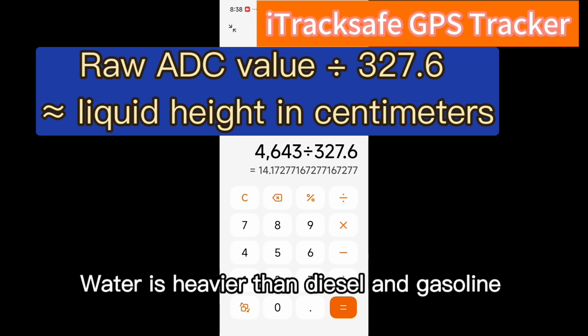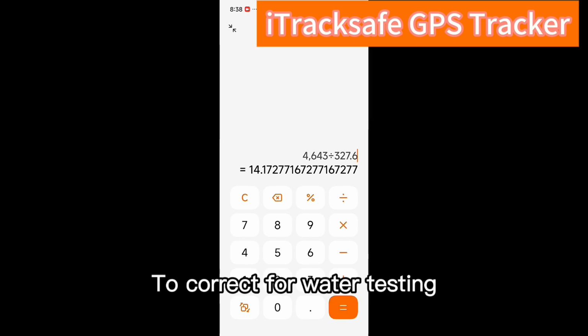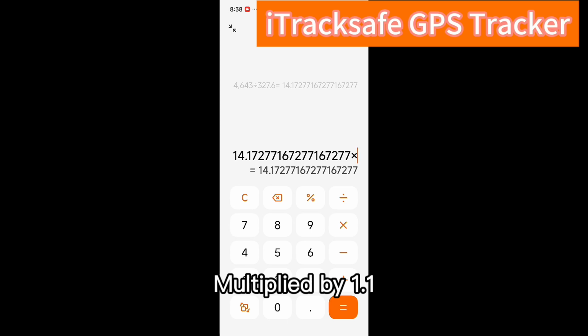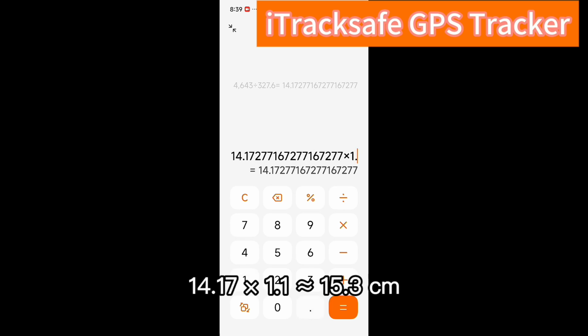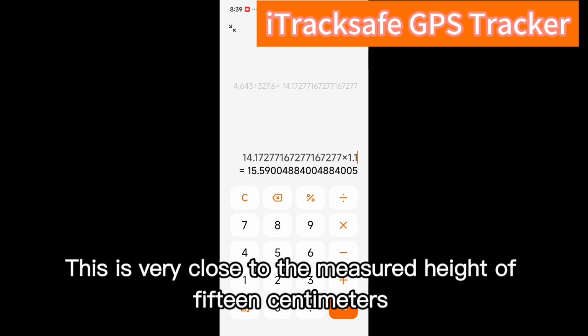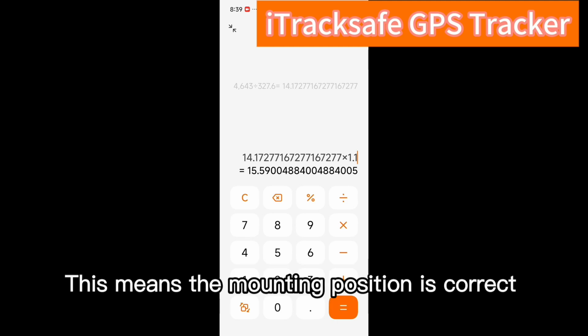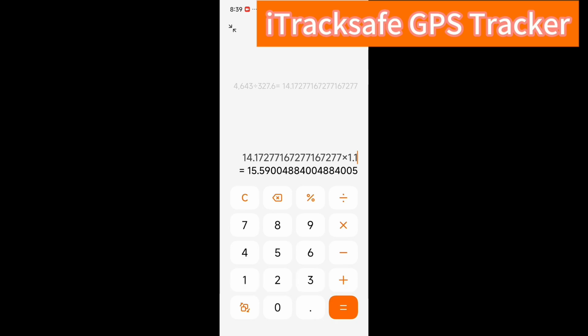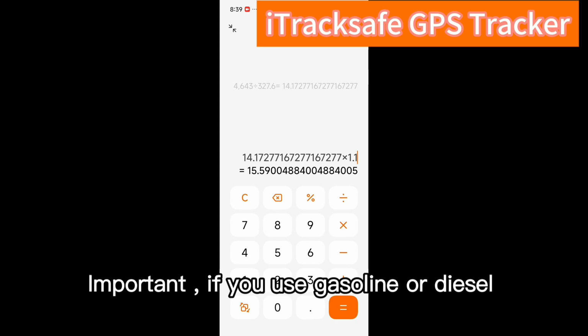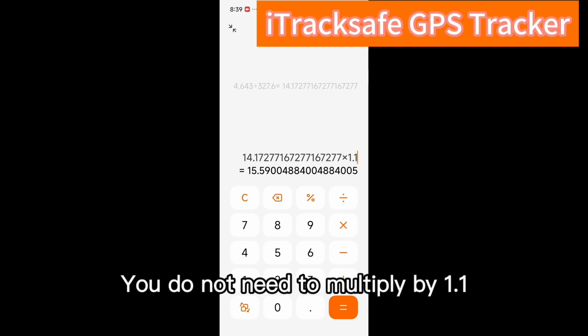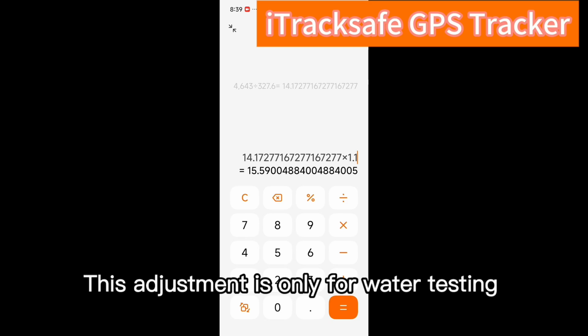Water is heavier than diesel and gasoline. To correct for water testing, multiply by 1.1. 14.17 times 1.1 equals 15.59. This is very close to the measured height of 15 centimeters. This means the mounting position is correct. Important: if you use gasoline or diesel, you do not need to multiply by 1.1. This adjustment is only for water testing.